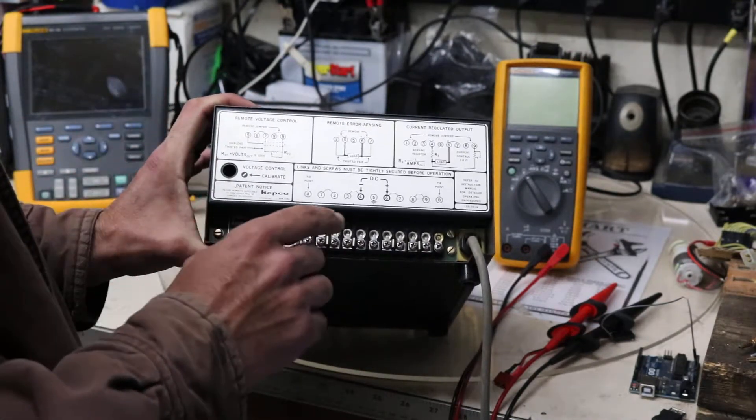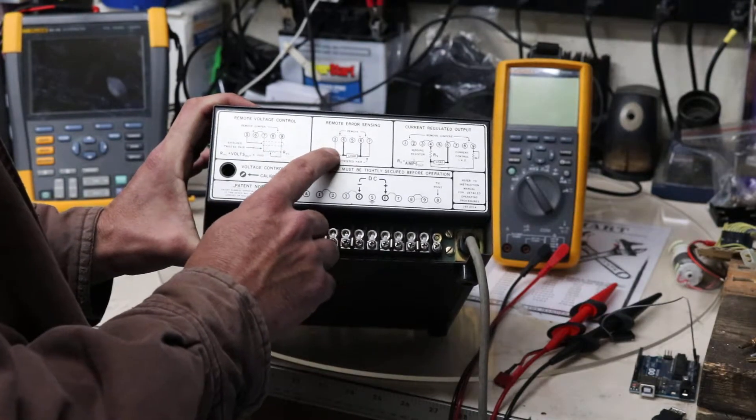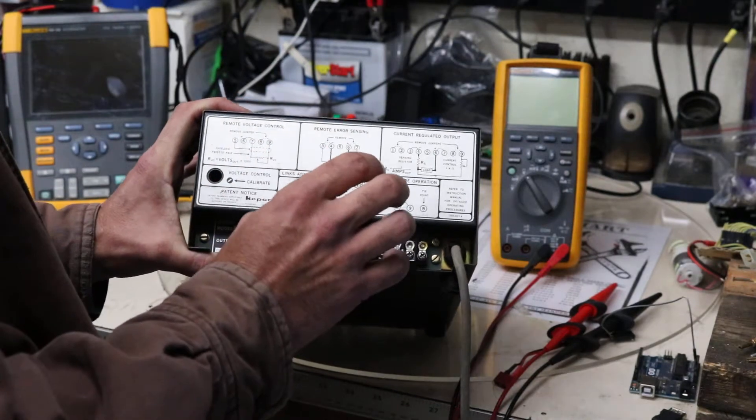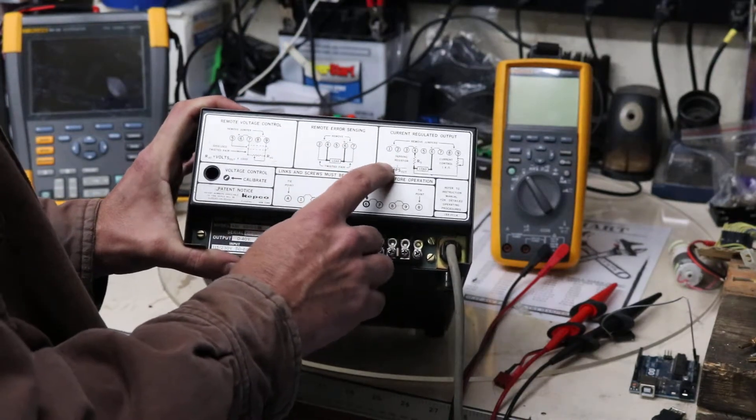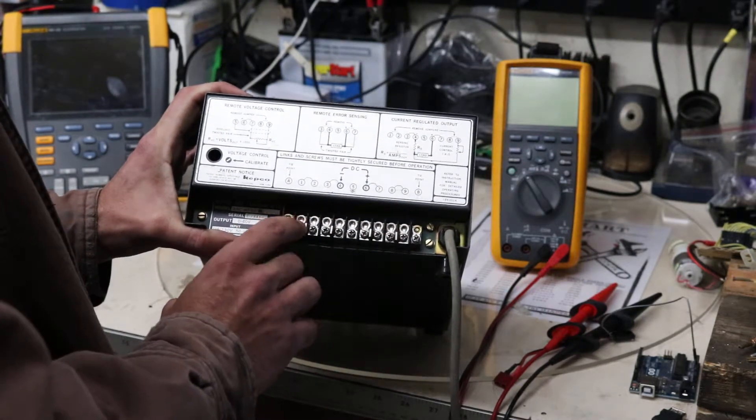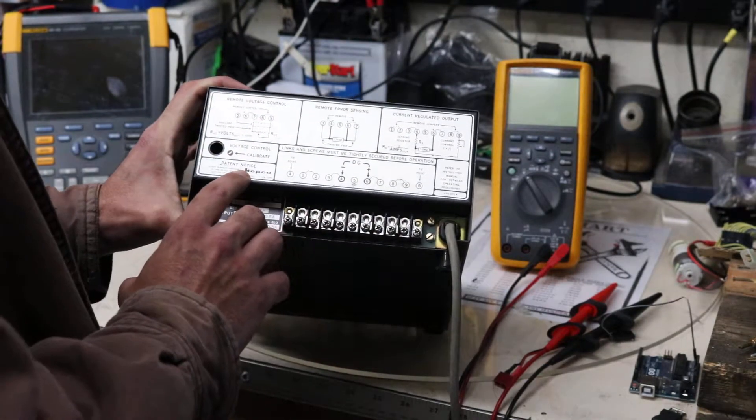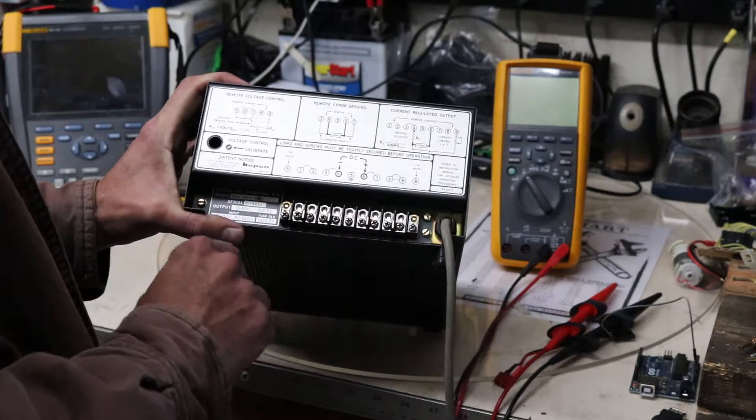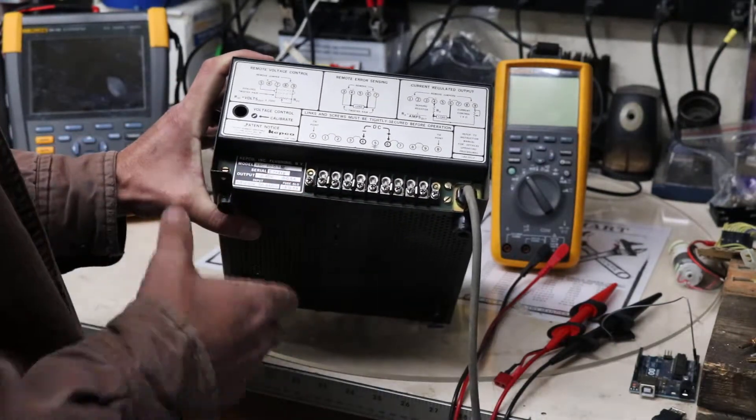This is if you wanted to put an external potentiometer somewhere else besides the front of the power supply to adjust the voltage. Remote error sensing, which would determine probably short circuits, things along those lines. And then our current regulation output, which you can set back here, hook up stuff back here instead of on the front terminals if you had something that needed a dedicated power supply but you didn't want to use the banana plugs on the front of it.